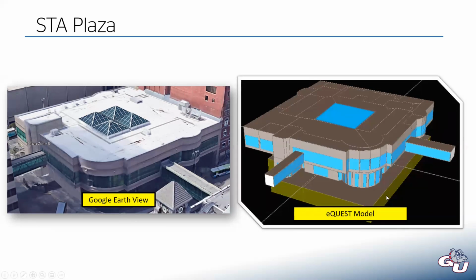So I used the program eQuest to create this entire building to run my simulations. So I created a model that not only has all the building structure components, all the walls and the roof and what those are constructed out of based on U values, assumed infiltrations, and then I also have to create all of the mechanical systems. So I had to create systems for the multi-zone air handlers, the heat pumps, the rooftop units, all of that stuff has to go into that model.